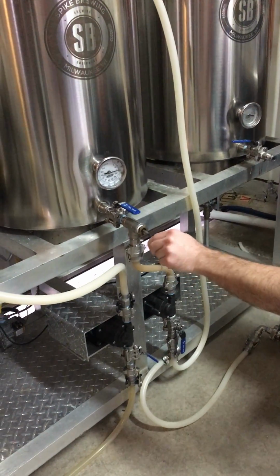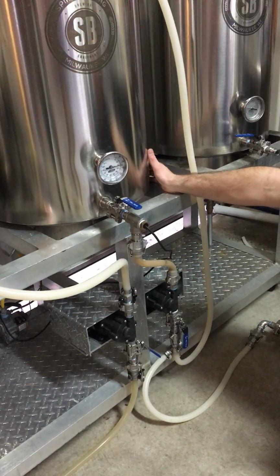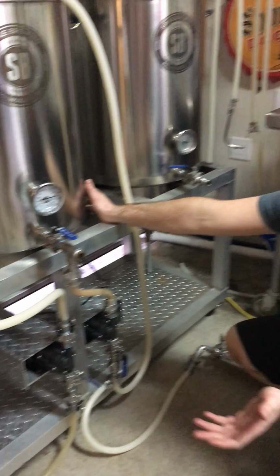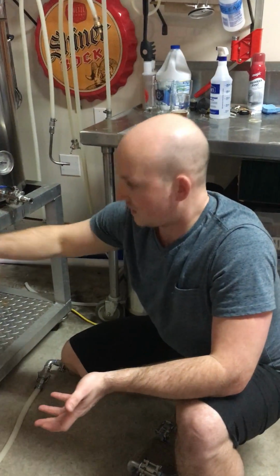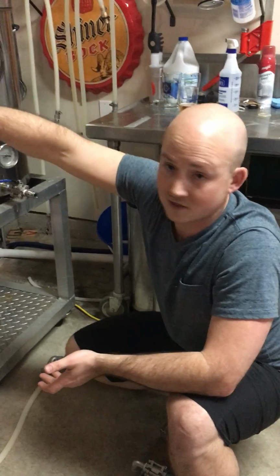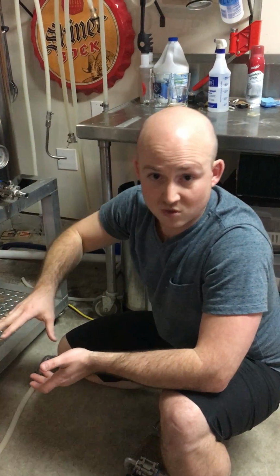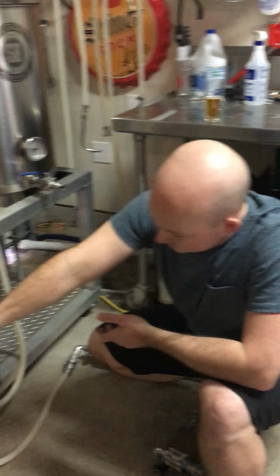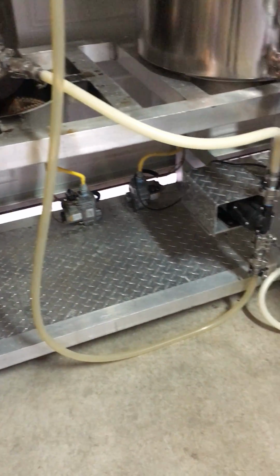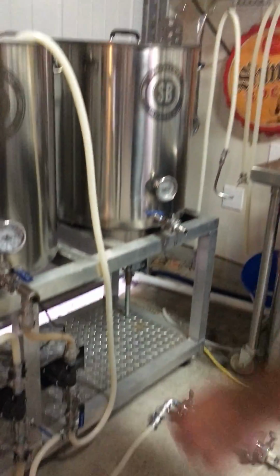This probe measures the liquid coming out of the bottom of the vessel. If it's too hot, it kicks the burner off, and it keeps recirculating through the pump back into the vessel. If it's too cold, it kicks the burner on with those electronic gas valves and starts heating it back up. It works pretty well as a process system - you have to monitor it, but mostly you just set the temperature and let it roll.